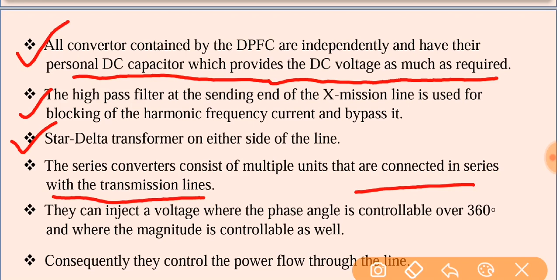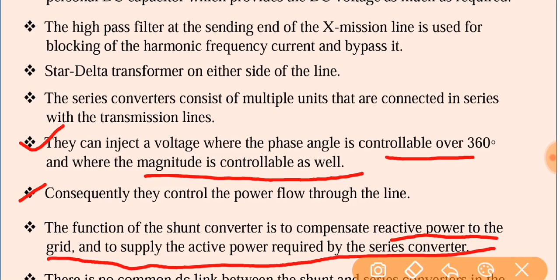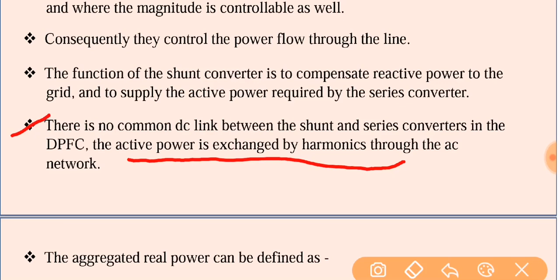Then the series converters inject a voltage where the phase angle is controllable over 360 degrees and where the magnitude is controllable as well. Consequently, they control the power flow through the line, and the function of the shunt converter is to compensate the reactive power to the grid and supply the active power required by the series converters. There is no common link between the shunt and series converter in the DPFC. The active power is exchanged by harmonic through the AC network.